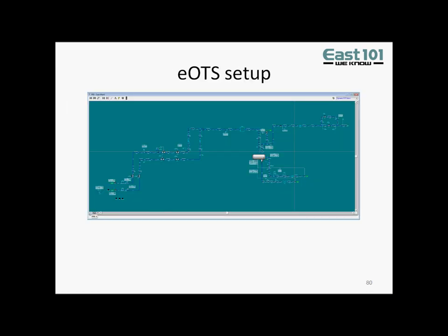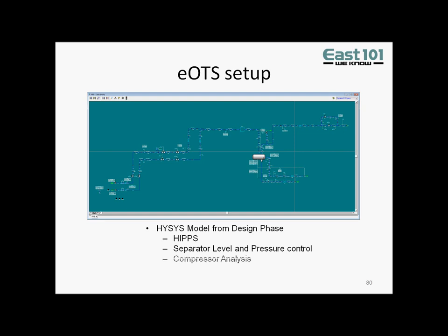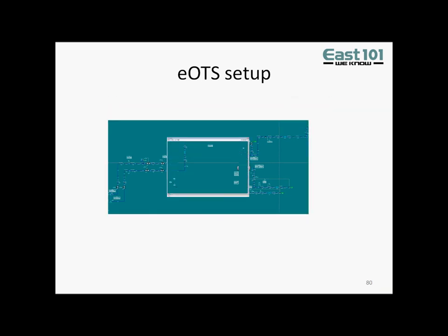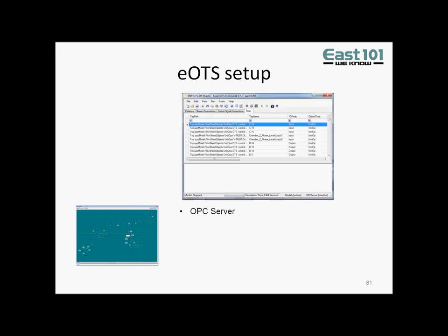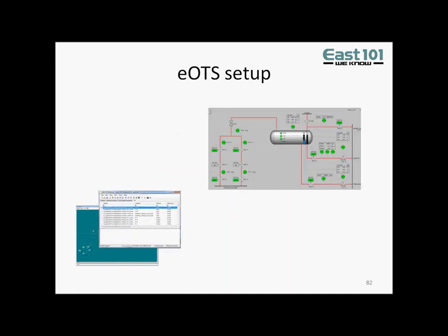Here's how the EOTS was set up. We start with a dynamic simulation model. This example shows a HYSYS simulation used in the design phase for several analyses — for example, a HIPPS study involving blocked outlet, a separator level and pressure control study involving severe slugging, and a compressor analysis involving emergency shutdown. As you can see, the simulation may cover a wide range of operations. However, this is not seen by the EOTS end user. On top of the simulation is an OPC server, which connects to HYSYS and exposes tagged variable values to OPC-compliant software. The OPC server links HYSYS and the Human-Machine Interface. The role of HMI is fulfilled by an OPC-aware graphical user interface that can be freely customized so that it looks familiar to operators and is easy to use.